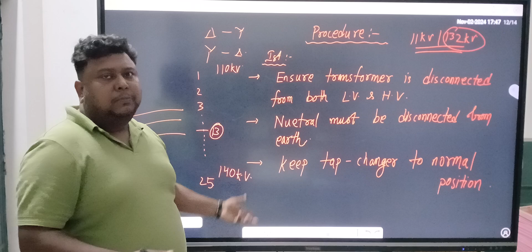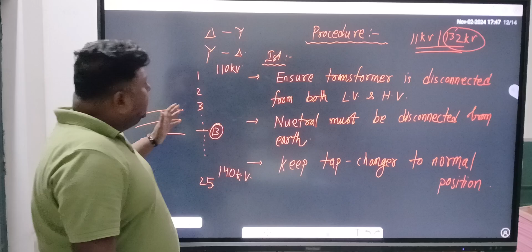For example, the transformer is 11 kV by 132 kV, right? If this is the rating of the transformer, so this secondary side, always you know tapping is under HV side. So this secondary or the HV side 132 kV will be having the range from 110 kV to 140 kV. This is the tapping, or this is the meaning of tapping. Sometimes we don't know what is the transmission voltage given. It cannot be 132 always. Sometimes there is voltage sag, sometimes there is voltage swell. So under each and every condition, this 132 kV frequently changes. Sometimes it is working under 110, means 110 is the supply voltage. Sometimes it is coming to the maximum value of 140.